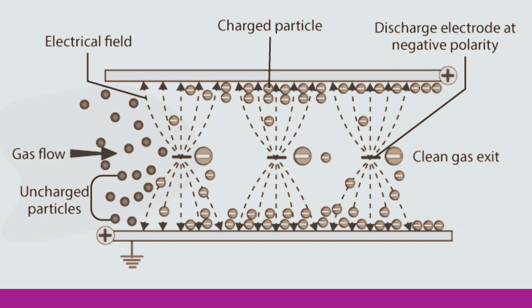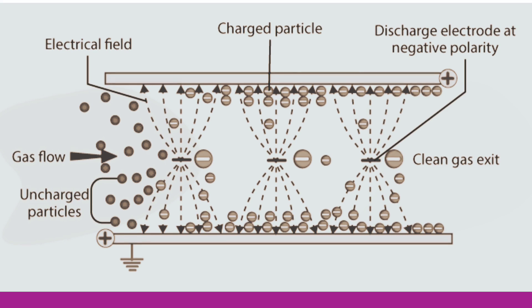A high voltage system provides power to the discharge electrode to generate an electrical field. The particulate entrained in the gas is charged while passing through the electrical field. The particulate is then attracted to the grounded collector plate and forms a dust layer on the plate.